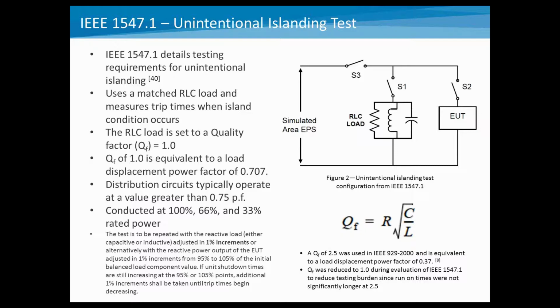The other thing that's mentioned on this slide is something called a quality factor. The quality factor in the test is now equal to 1, and that is equivalent to a worst case power factor of 0.7. When we were designing and developing these tests, we wanted to create basically a resonant circuit that would try to hold the device at 60 hertz, or 50 hertz if you were doing a European standard system. So basically what this does is it sets up what's called a resonant tank circuit. That RLC load is very tightly matched. It also has the ability, using the L and C, to create a way to hold that frequency steady so that the devices can't necessarily push it around.